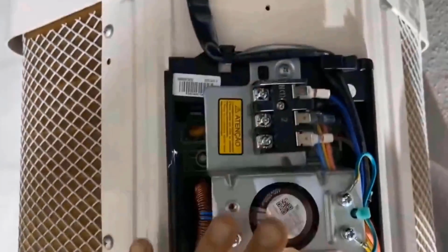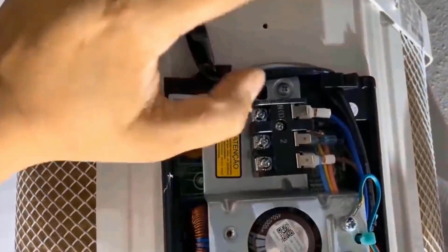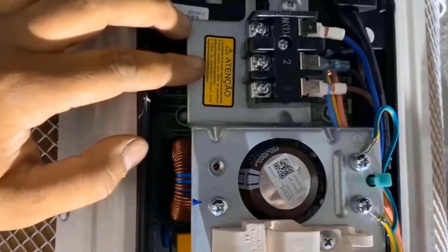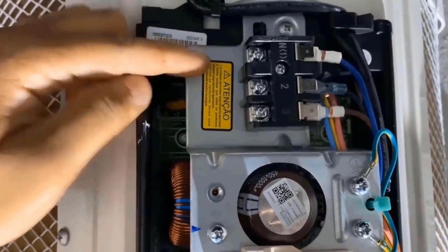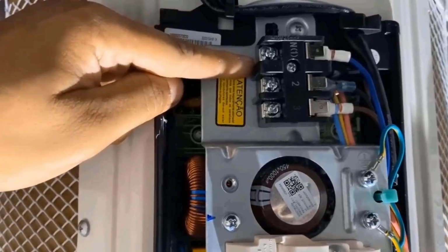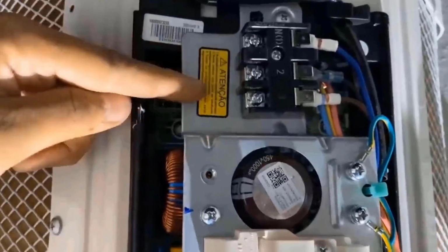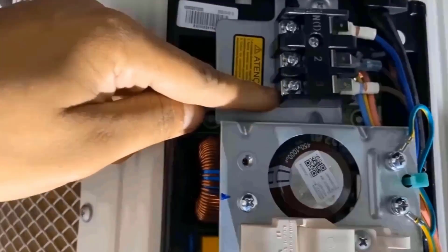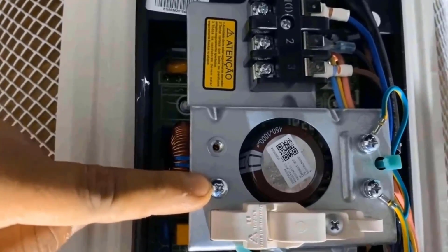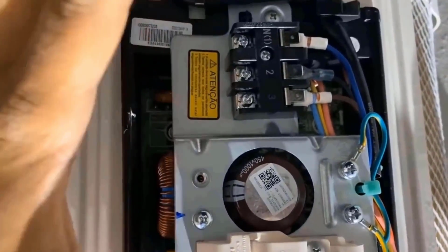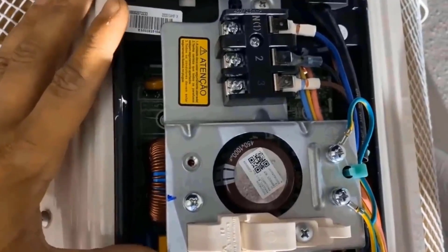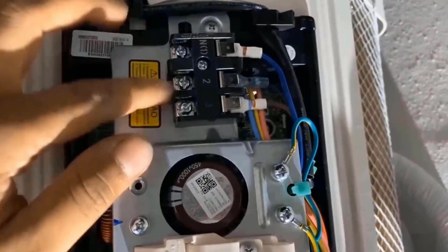If you have encountered this problem, it indicates that it is precisely a communication failure between the evaporator and condenser units. Now, how can this happen? If by chance the wires that communicate between the evaporator and the condenser have been reversed, the error will appear. Another possibility is if the wires are poorly connected or if there is a problem with the board.